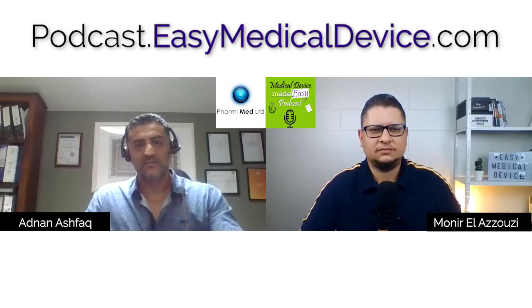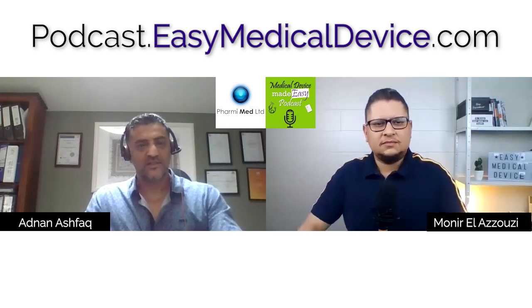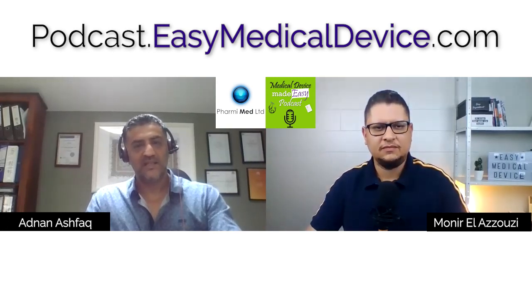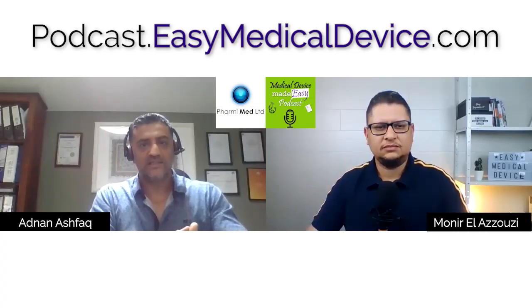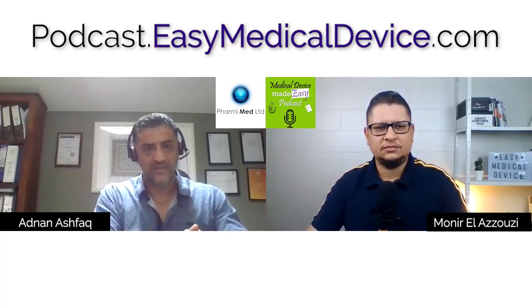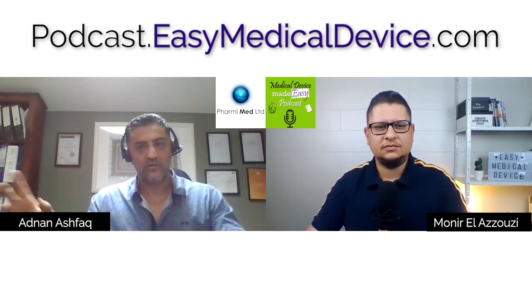Immediately can lead to death. On the other hand, we might have some predicting software which is predicting that somebody has cancer and they're going to die in 6 months. So the safety classification may be a Class C because it can lead to death, or it might be a Class B because it's not immediately going to lead to death, but long term it can. So here we have an argument to lower the safety classification from a Class C to a Class B, but within the overall MDR classification, it might still be a Class 3.